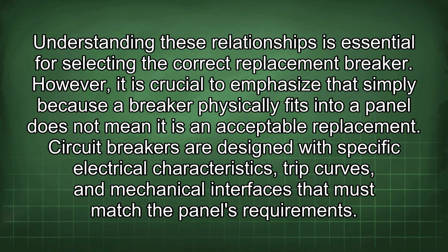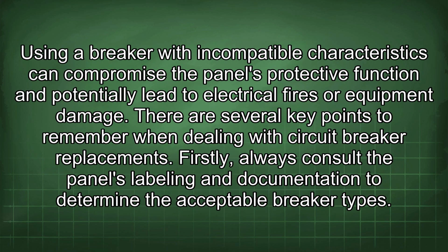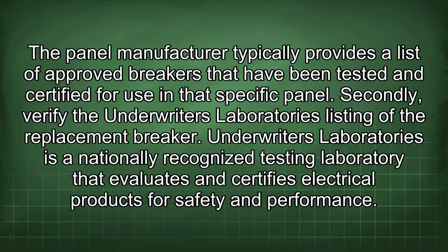However, it is crucial to emphasize that simply because a breaker physically fits into a panel does not mean it is an acceptable replacement. Circuit breakers are designed with specific electrical characteristics, trip curves, and mechanical interfaces that must match the panel's requirements. Using a breaker with incompatible characteristics can compromise the panel's protective function and potentially lead to electrical fires or equipment damage. There are several key points to remember when dealing with circuit breaker replacements. Firstly, always consult the panel's labeling and documentation to determine the acceptable breaker types. The panel manufacturer typically provides a list of approved breakers that have been tested and certified for use in that specific panel. Secondly, verify the Underwriters Laboratories listing of the replacement breaker.